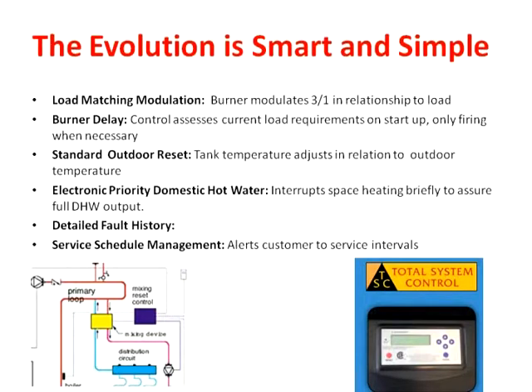So this unit can actually go up to 160 degree supply water temperature out to the system if you want to set the unit as high as 180 degrees in the most extreme conditions out there. Typically that would be saying you're using some sort of radiator or higher temperature product. More typically, let's say 140 degrees and down, the maximum temperature might go to 160 degrees in the tank. But again, the outdoor reset takes care of that. You just have to put in the parameters of how low do you want to go, which would be not lower than your domestic hot water temperature you want, and how high you want to go, and then just the reset curve, and it will do it automatically.